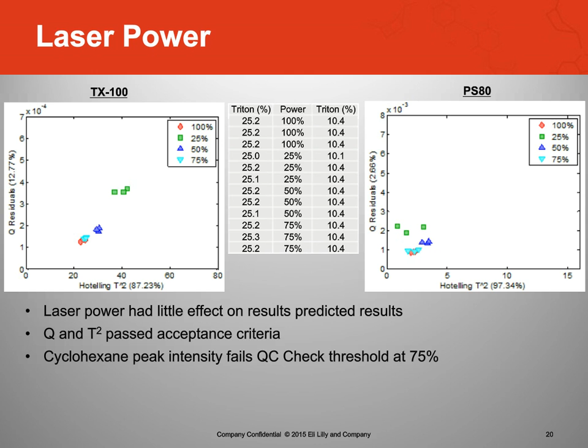So here's where we talk a little bit about laser power. The cyclohexane, our QC check, fails at a 75% threshold. In all these cases, we went from 125, 100, 75, down to 25, and in all cases they passed the model, so I just looked at repeatability. We get results consistently across the board of 25.2, 25.1, and then 10.4. There was really no impact of laser power. Basically, the bottom line is laser power has no impact on the result. However, we would catch it with our cyclohexane check at a 75% threshold.